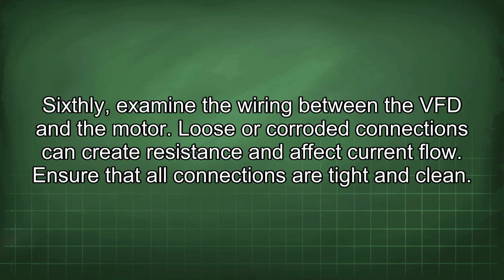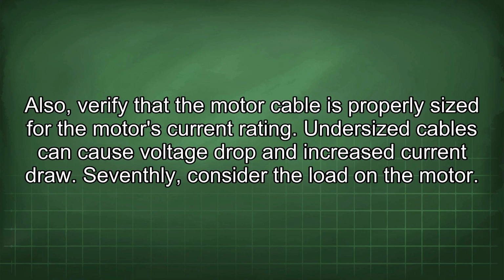Sixthly, examine the wiring between the VFD and the motor. Loose or corroded connections can create resistance and affect current flow. Ensure that all connections are tight and clean. Also, verify that the motor cable is properly sized for the motor's current rating. Undersized cables can cause voltage drop and increased current draw.